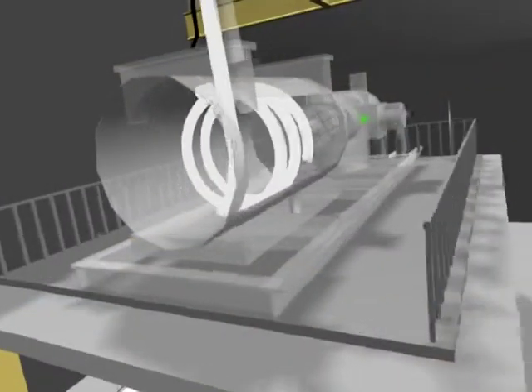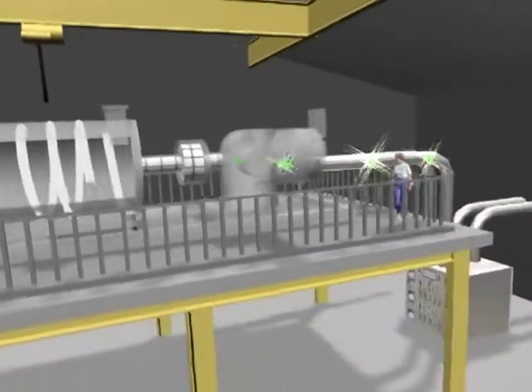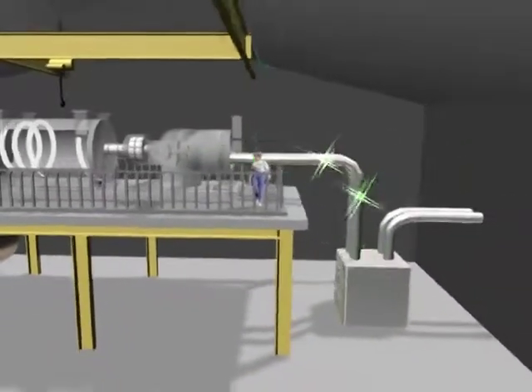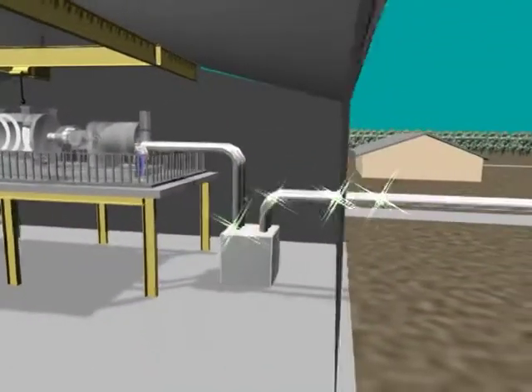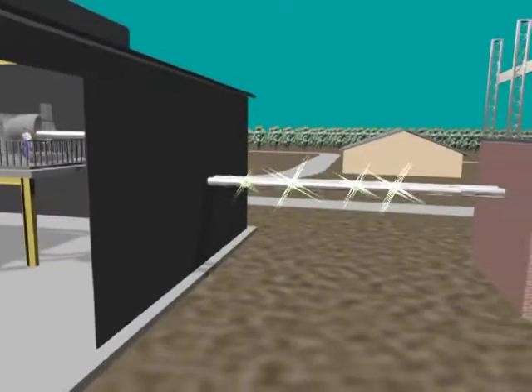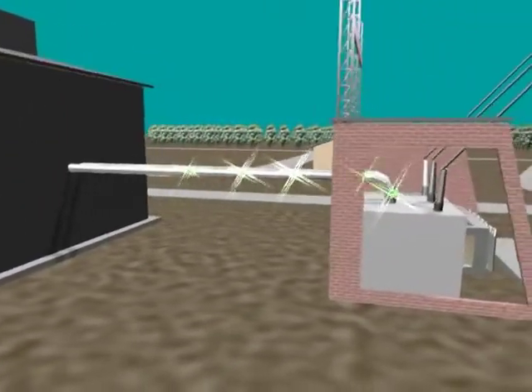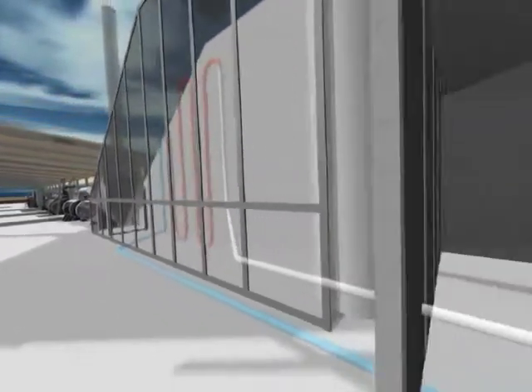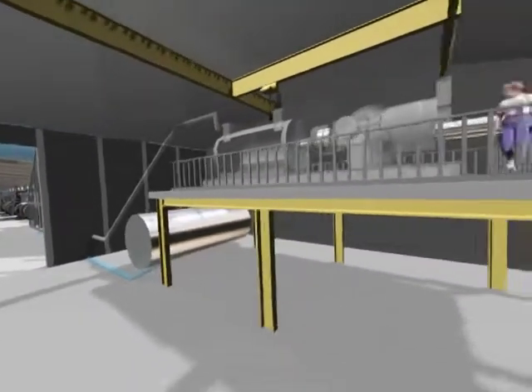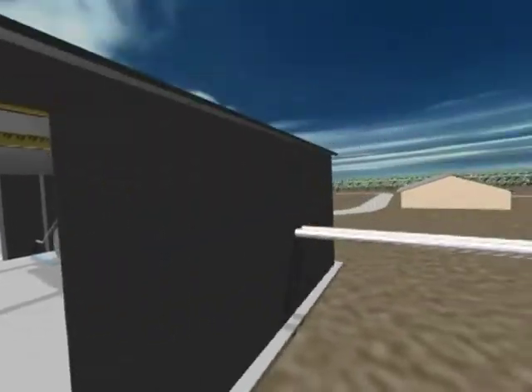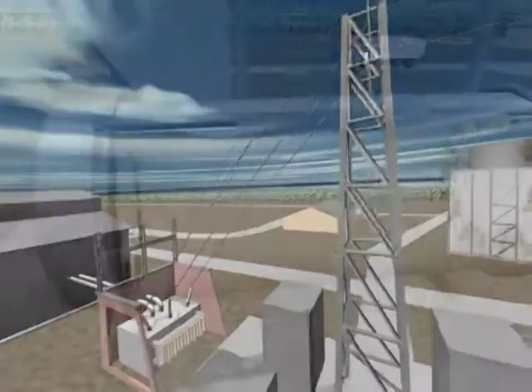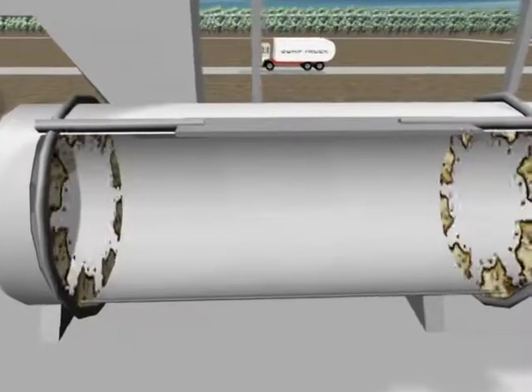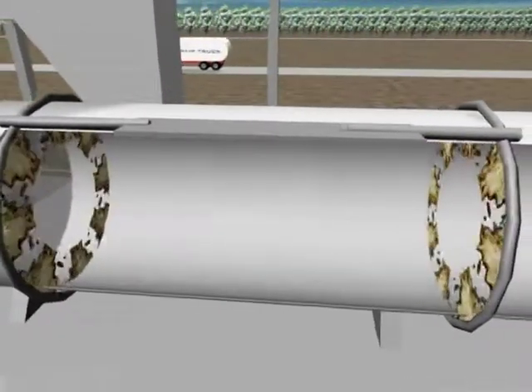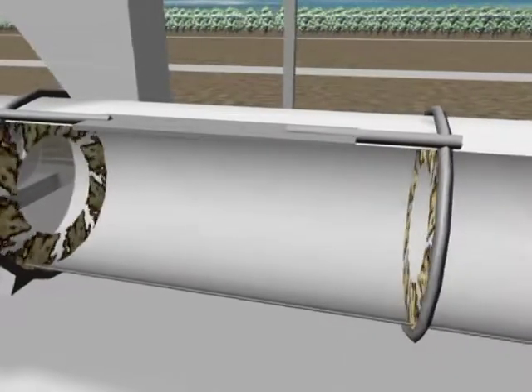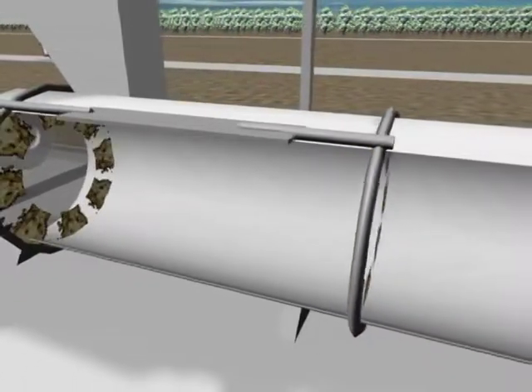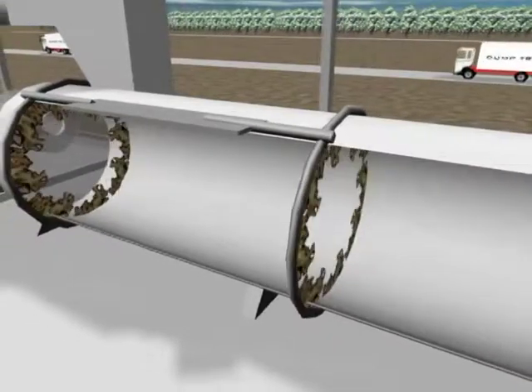The amount of steam generated is directly related to the energy content of the waste feedstock materials, and power generated from the steam can be between 35 and 60 megawatts depending on design considerations. Even if one unit is out of service, the plant remains operational and continues to process the waste material and generate electricity. If the waste fuel stream is ever interrupted, the thermal oxidizer is engineered in such a way that it can be used similar to a duct firing arrangement to supplement the heat needed to maintain steam generation necessary for guaranteed power supply contracts.